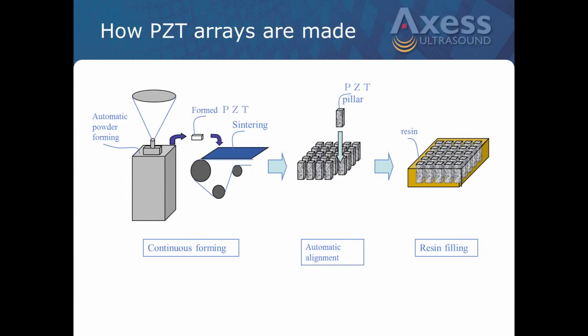Now, this is just a little diagram kind of showing you a very, very rough outline of how current composite PZT arrays are made. Basically, the manufacturers put in a powder. It's crushed raw earth crystal, and they form these actual arrays. I've seen this. I've been to several array manufacturing facilities, both with OEMs and independent array manufacturers. They're huge ovens. They heat these things up to several thousand degrees Fahrenheit, and then they create these blocks. Then once they form the crystal, it goes over, and this is obviously blown up dramatically, but these are individual elements. So they have to do an alignment on these and form these. Then they're usually put into a resin or epoxy block to hold the individual elements together. But again, it just gives you a ballpark view of how these arrays are put together.